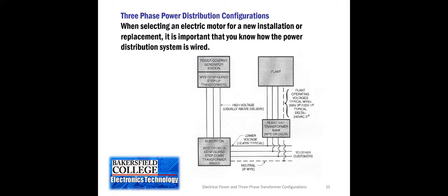powered by the utility. And so you'll have something like, let's say in this case, 12,470 volts, about 12,500 volts, and then the distribution transformer breaks it into the operating voltages that allow the devices inside that building to be powered.